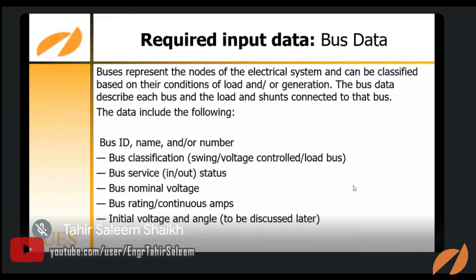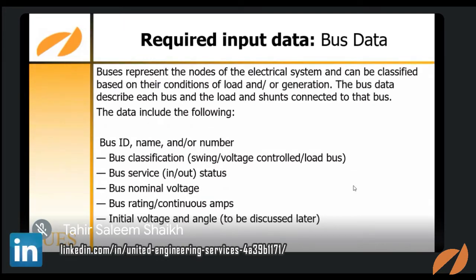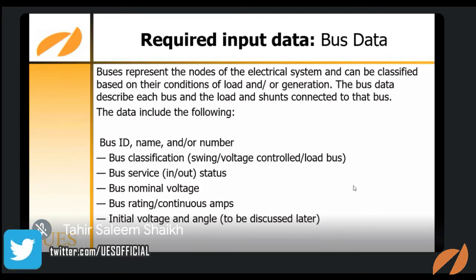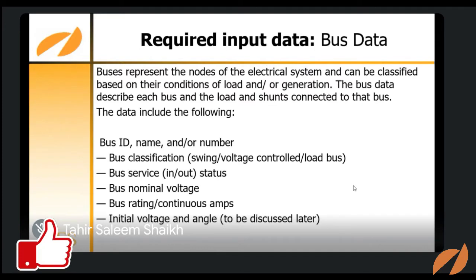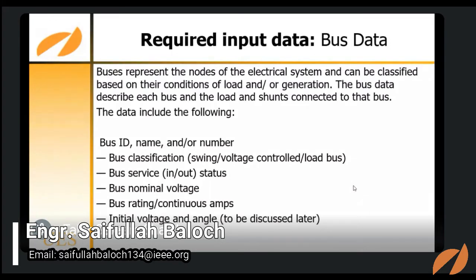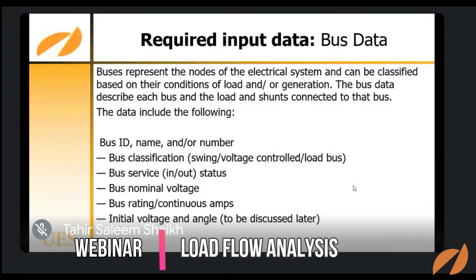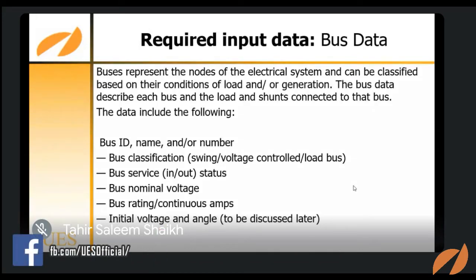Now bus rating and continuous amp: this depends upon the material which the bus is manufactured from, like copper, aluminum, or any other material which your computer based program gives you as an option. In many different programs we have different materials. In ETAP we have two types of material, copper or aluminum. On the basis of that material specification, it will allow you to select the ampere rating or continuous ampere rating. Initial voltage and angle, we are going to discuss in the next slides, inshallah.